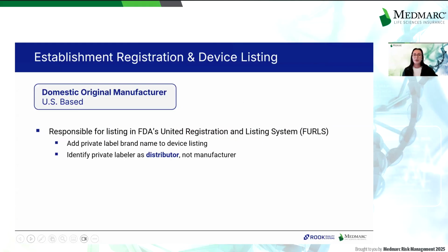For domestic OEMs based in the USA, it is their responsibility to maintain the device listing in the FDA's FURLS, or FDA Unified Registration and Listing System. When the device is marketed under a private label, the OEM must update the existing listing to indicate the private labeling brand and designate the private labeler as a distributor, not as a manufacturer. If the private labeler is solely engaging in distribution and does not perform manufacturing, relabeling, repackaging, or specification development, they are not generally required to register their own establishment with the FDA.